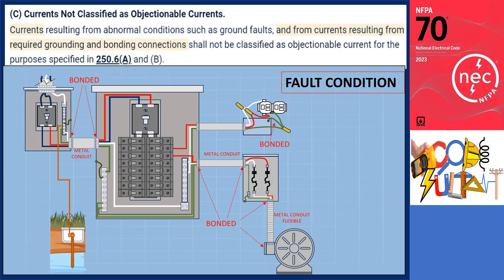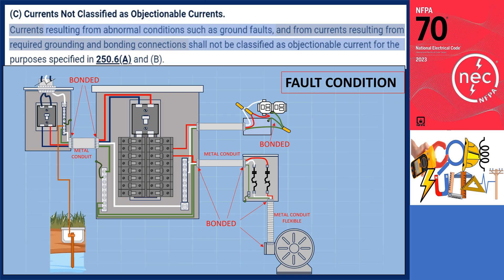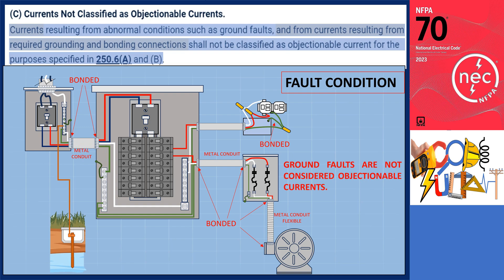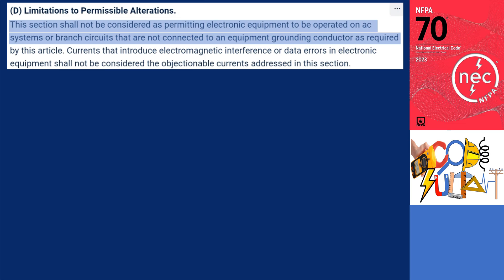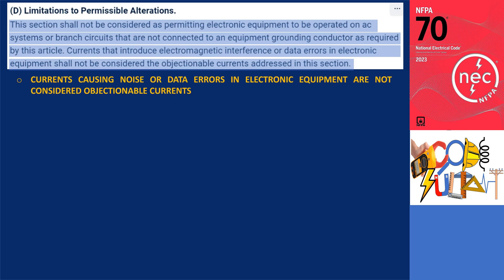Section 250.6C states that current resulting from abnormal conditions such as ground faults, and from current resulting from required grounding and bonding connections, shall not be classified as objectionable current for the purposes specified in 250.6A and B. The code clarifies that ground faults are not considered objectionable currents. Section 250.6D, limitations to permissible alterations: the provisions of this section shall not be considered as permitting electronic equipment to be operated on AC systems or branch circuits that are not connected to an equipment grounding conductor as required by this article. Currents that introduce noise or data errors in electronic equipment shall not be considered objectionable currents addressed in this section.